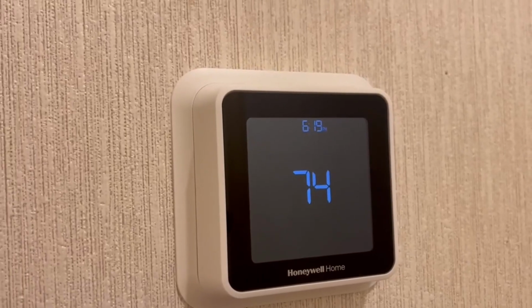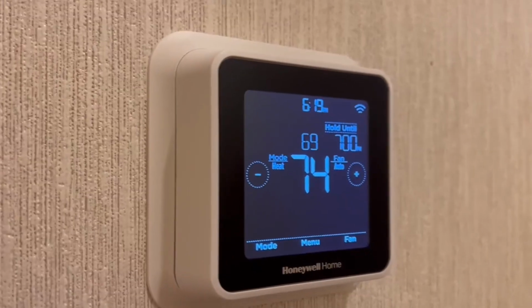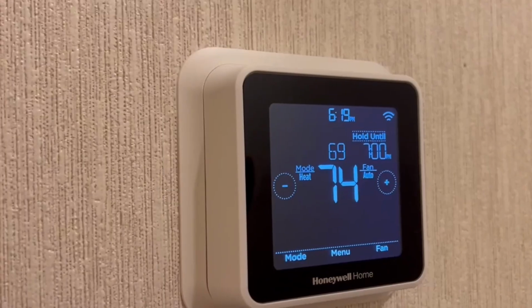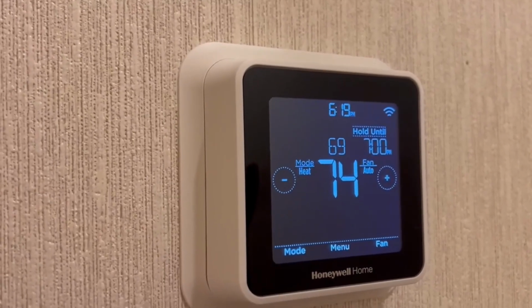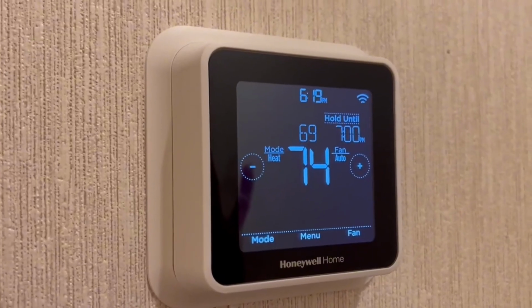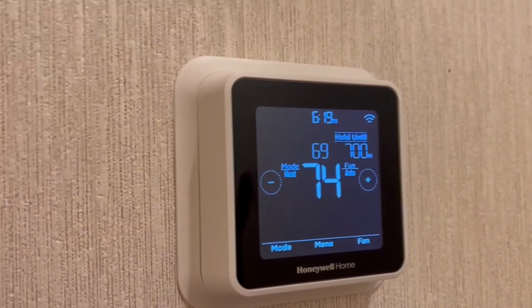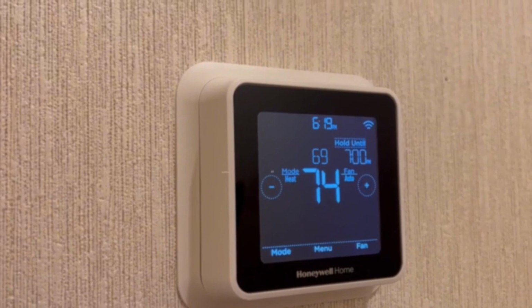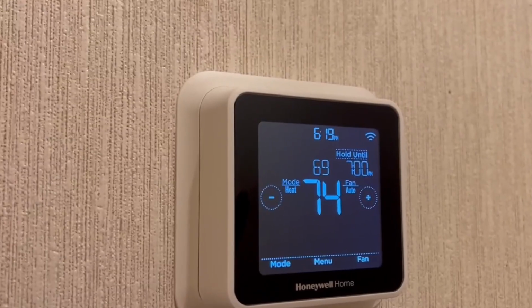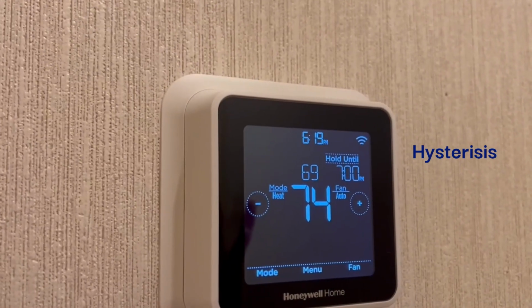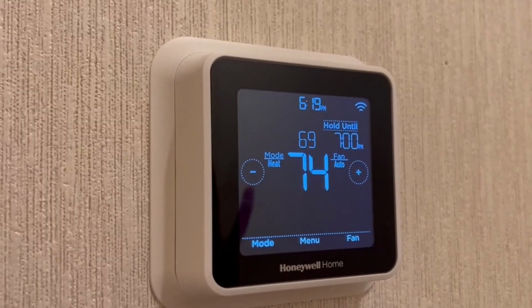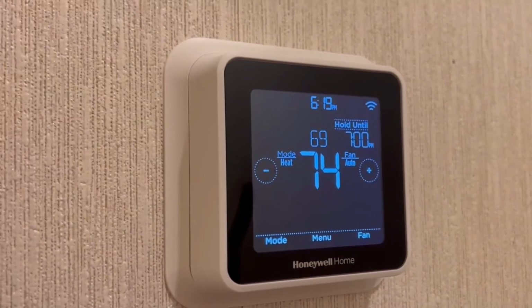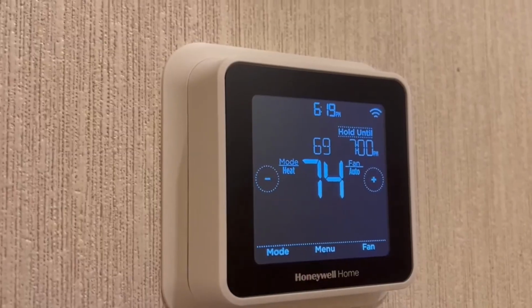Here's the core logic. The thermostat constantly compares set point temperature, what you want, and actual room temperature, what it senses. When the difference crosses a threshold, it sends a signal. Either heat on, cool on, or system off. This on-off logic uses something called hysteresis, which prevents rapid cycling. And again, turning it way up doesn't make heat arrive faster. It just delays when the system turns off.